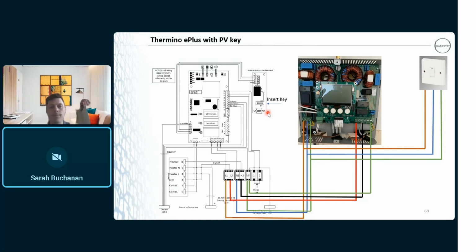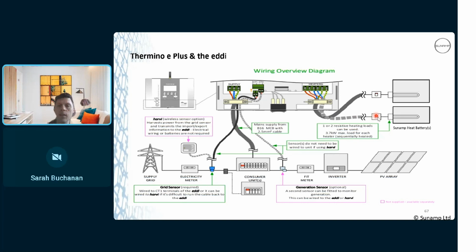Someone's just asking, is there a maximum inlet temperature if in series? A maximum inlet temperature? No. Not at all. If you think about it, if your secondary battery is up to temperature, and the output of that is up to 70 degrees, boom, that's going into your primary battery. That's going to benefit this battery because there's going to be no heat exchange going on, isn't there? So even better.